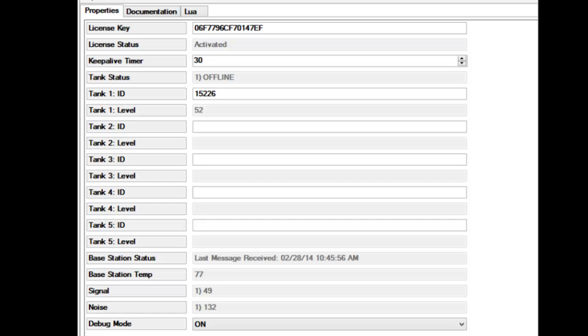Now, let's review some of the items on the Properties tab of the driver. Keep Alive Timer: This timer changes tank status to Offline if it has not heard a response in X number of minutes. Recommended to leave this default at 30.